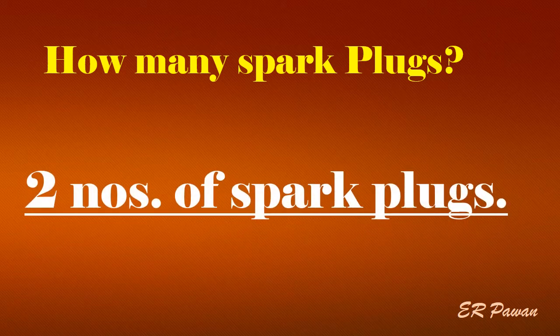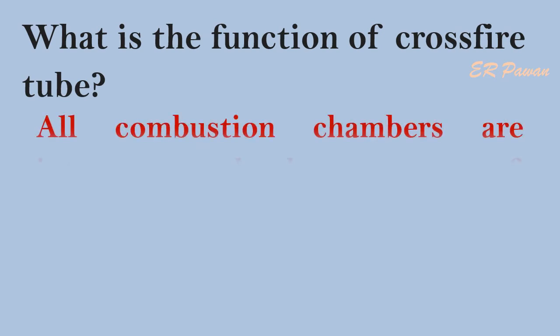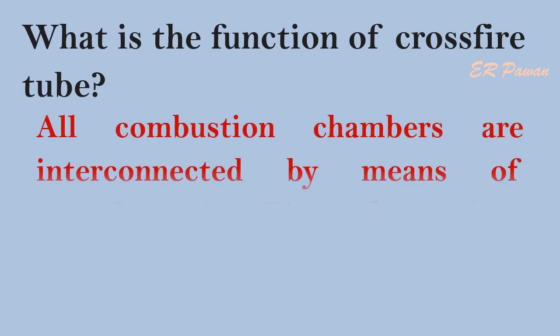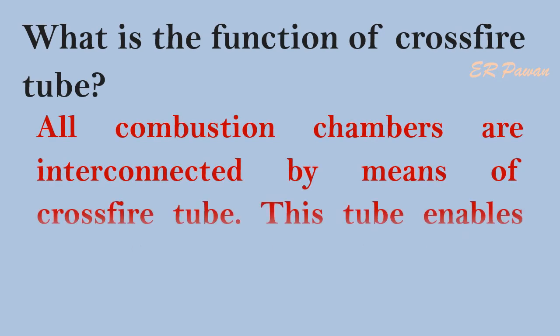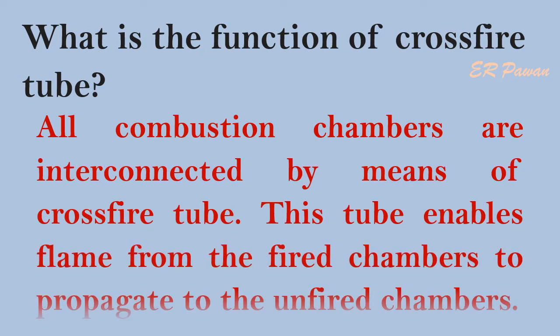How many spark plugs are used in the turbine? 2 numbers of spark plugs. What is the function of the cross fire tube? All combustion chambers are interconnected by means of a cross fire tube. This tube enables flame from the fired chambers to propagate to the unfired chambers.